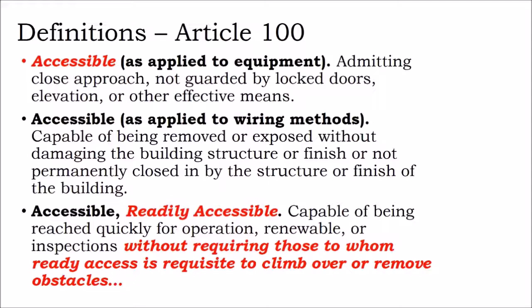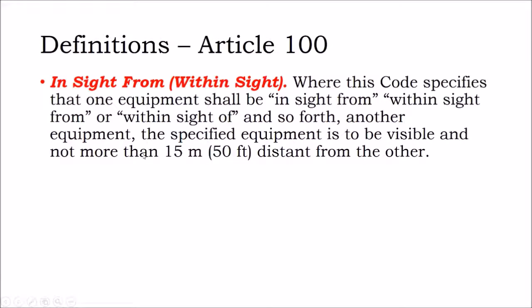So accessible is that the device can be easily approached. Readily accessible is a little bit different. It's being quickly approached. And the spirit of readily accessible is essentially without requiring people to grab a tool, or to grab a ladder or something like that to get access to that disconnect, so you don't have to climb over obstacles. So accessible means that you can get to it, but readily accessible means you cannot use any tools other than perhaps a key to open up the accessible device. So something that is permanently enclosed into the building facade would not be considered accessible. And then there's also a definition of in sight from, which is typically where you can see it from point A to point B, and it's not greater than 50 feet.